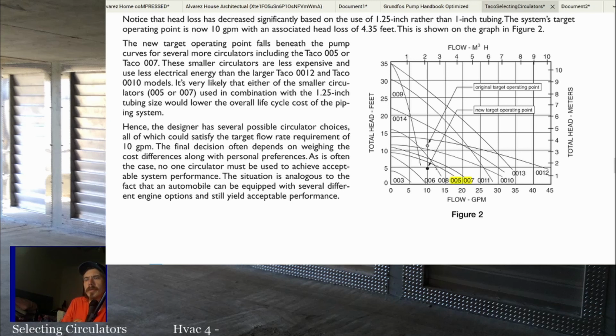Five's right here. So both these pump curves are close to that then. And so it falls below a Taco 005 or 007. Those are less expensive circulators and they use less energy. So if you're talking about energy efficiency, like I said, you use bigger pipe, it's generally going to be more efficient. You use bigger duct, you're going to have less static pressure in a system, right? So when it comes to something where you've got a circulator or a fan, generally the bigger you can make the pipe, the better.